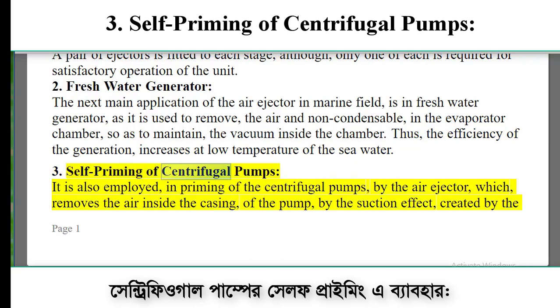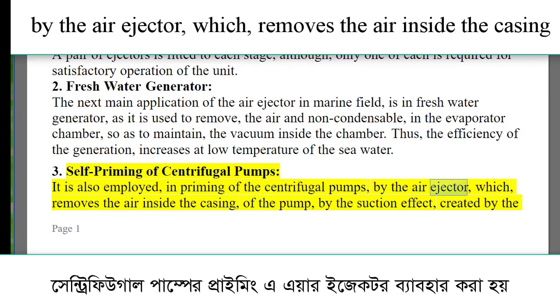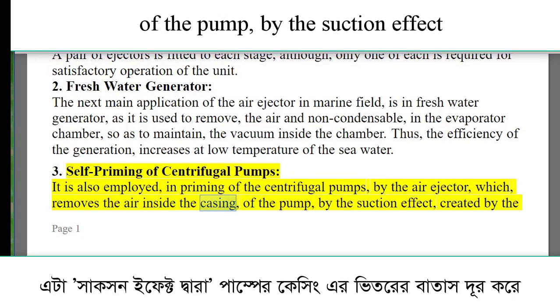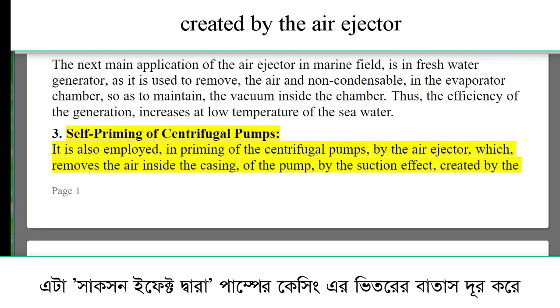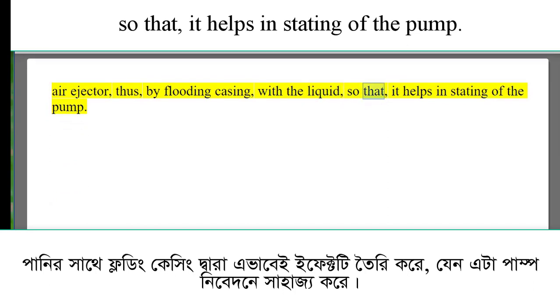Self-priming of centrifugal pumps: the air ejector is also employed in priming of centrifugal pumps, which removes the air inside the casing of the pump by the suction effect created by the air ejector, thus flooding the casing with liquid so that it helps in starting of the pump.